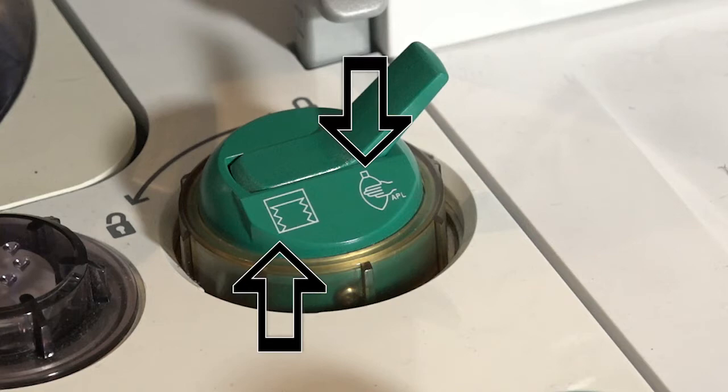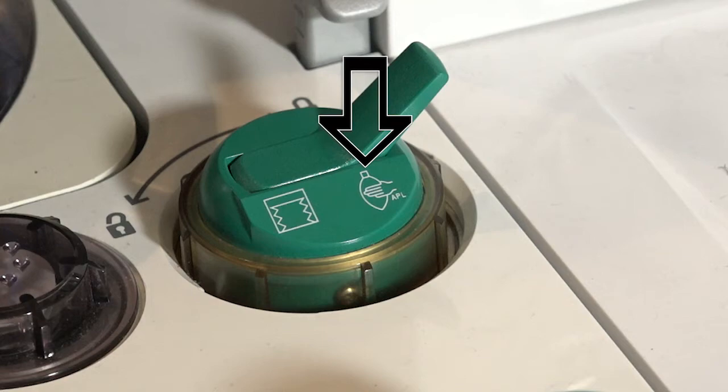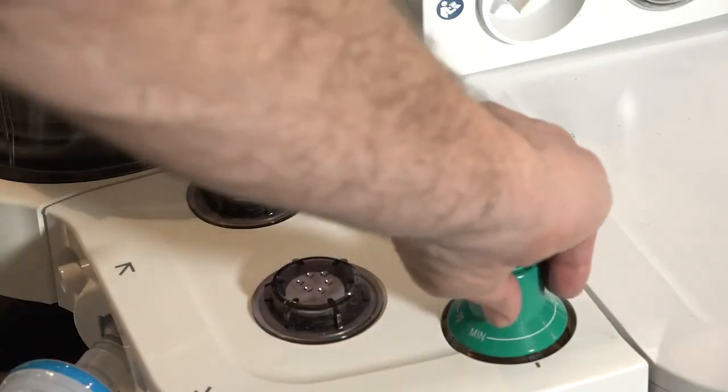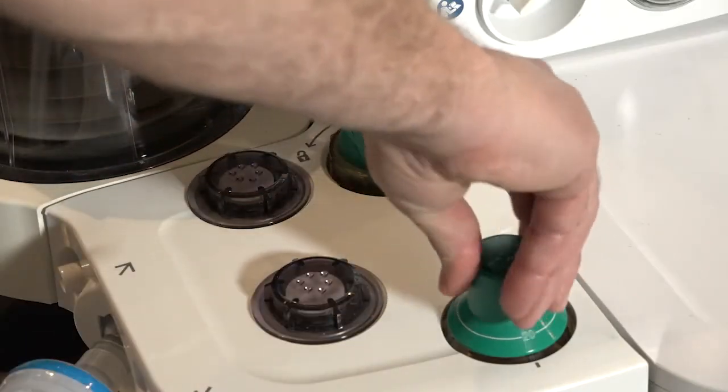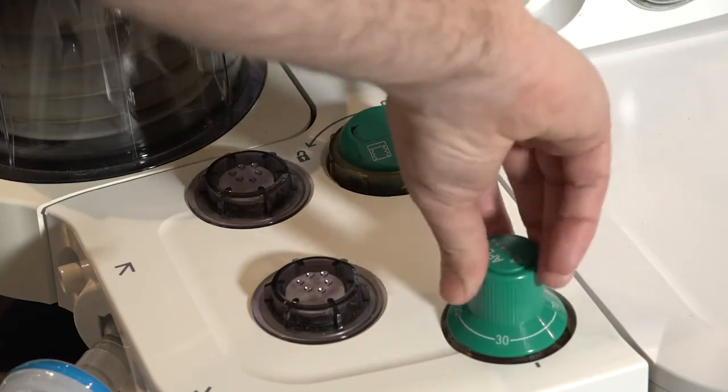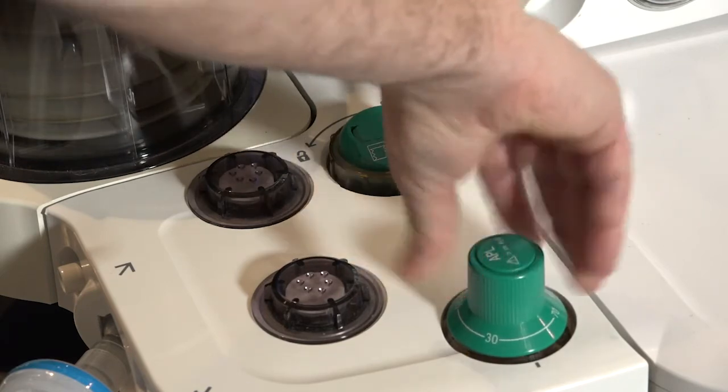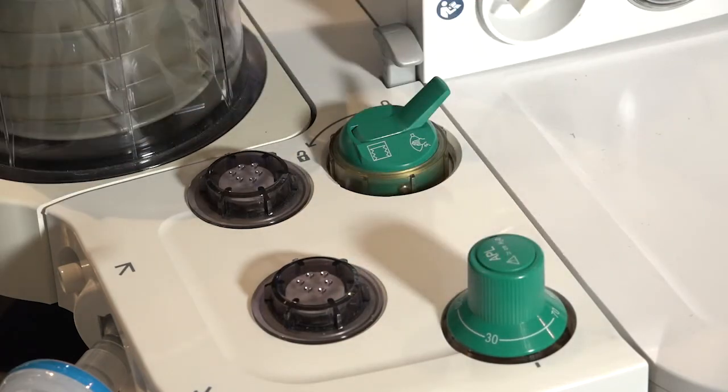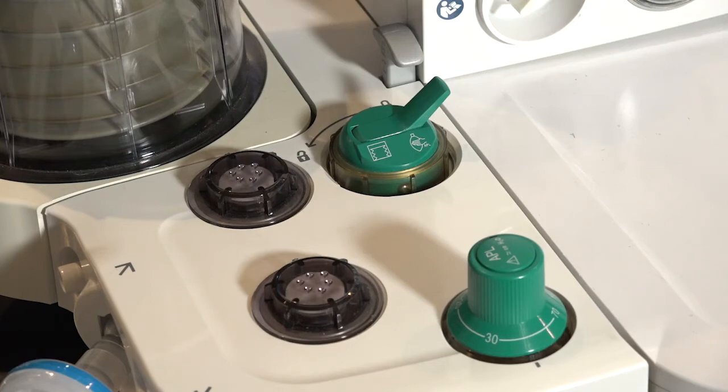When the device is in bag mode, the device is not providing any ventilation support to the patient. When the device is in manual ventilation, maximum pressure is managed by the adjustable pressure limit or APL valve. If ventilating the patient manually, ensure the APL pressure limit is appropriate for the patient.